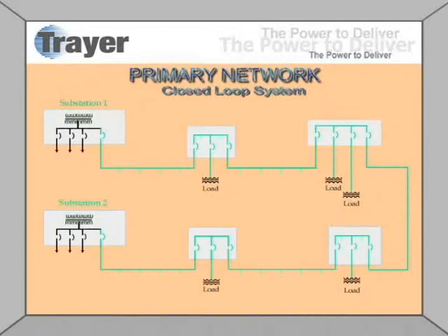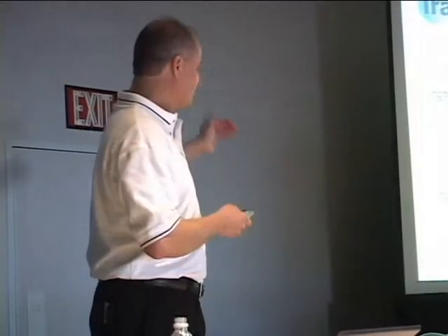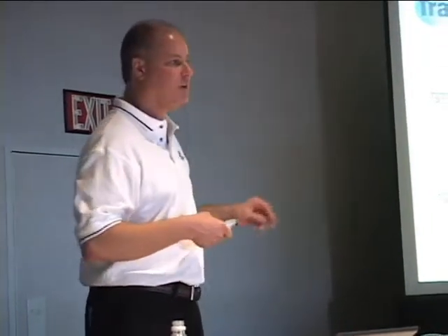Let's look at a closed-loop system, a primary network. First of all, there is no open point in this loop. This substation is tied to this other substation continuously. You don't have to have two different subs. You could have two feeders out of the same substation feeding the loop. That's common. But you could also have 3 or 4 different substations feeding this loop. There's really no limitation. The more sources of power you can bring into the loop, the better the system reliability will be, the more alternate sources of power that are available.